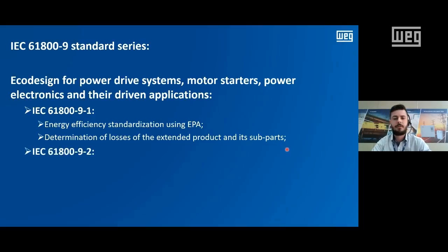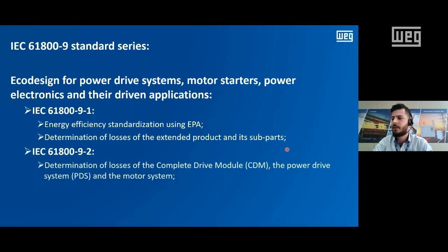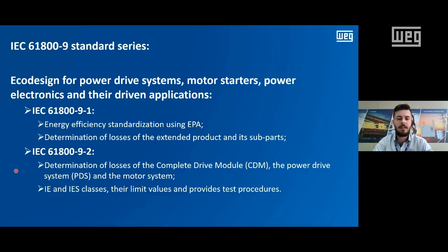And part two, which is more the field of the variable speed drives, talks about the determination of losses of the complete drive module. We are going to come to these terms later: the power drive systems and the motor system. As well, this standard also talks about the determination of IE classes and IES classes and their limit values of losses, and it also provides test procedures.